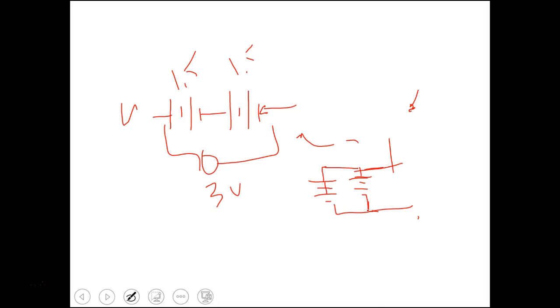So what we're going to do: if I want a divide by 2, then we need less current, we need less turn ratio on the primary side. But if the voltage goes down, the current is going to have to go up in the primary. So what we want to do is split those currents between the two coils, because this coil might be rated at 1 amp, this coil might be rated at 1 amp - if we hook them in parallel, then we can put 2 amps into the thing.